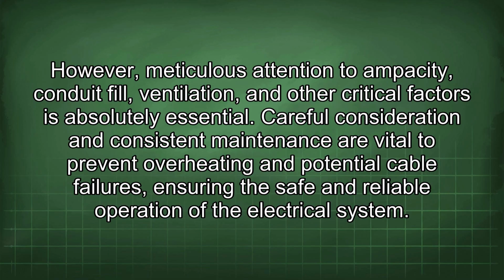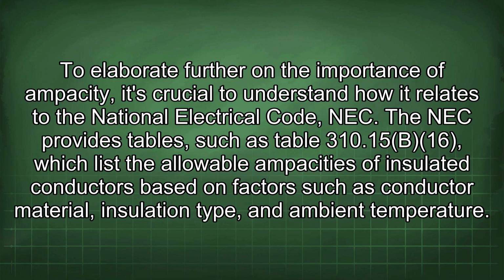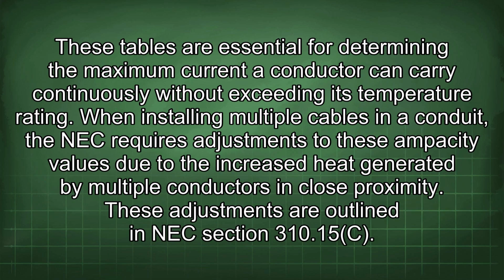of the electrical system. To elaborate further on the importance of ampacity, it's crucial to understand how it relates to the National Electrical Code, NEC. The NEC provides tables, such as Table 310.15(B)(16), which list the allowable ampacities of insulated conductors based on factors such as conductor material, insulation type, and ambient temperature. These tables are essential for determining the maximum current a conductor can carry continuously without exceeding its temperature rating.